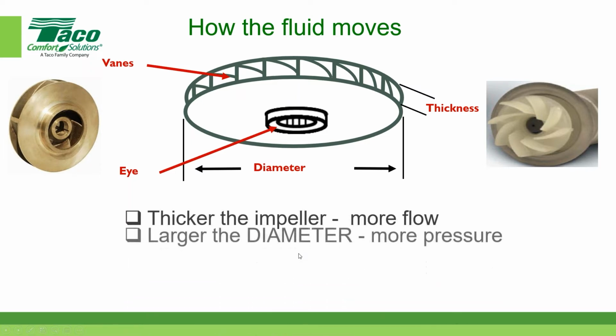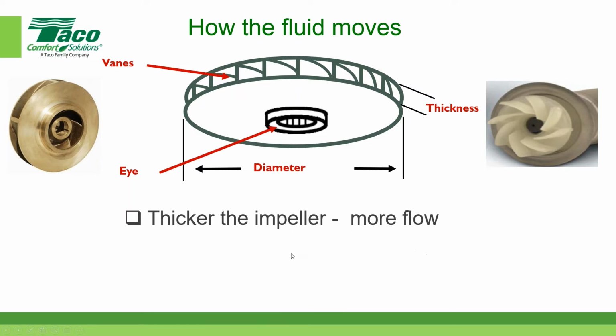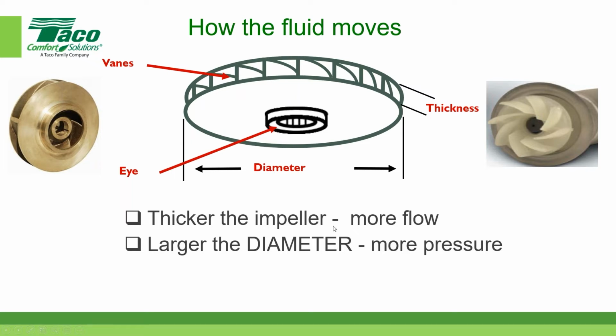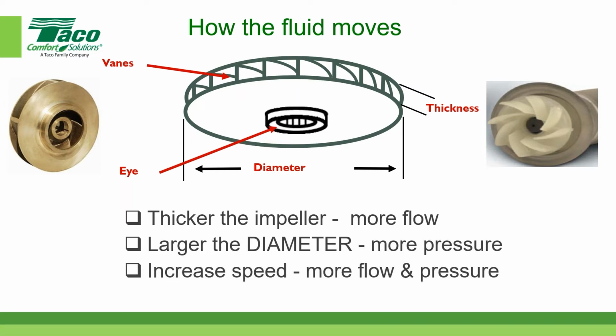Okay. So another thing to remember: the larger the diameter... well, let me reference something real quick. The thicker the impeller, the more the flow. Remember the bucket analogy with the little girl spinning it? This would be akin to how big that hole is. The diameter would be how long the rope was at a given RPM. That little rope that she had on the bucket, if it got longer and she stayed at the same RPM, you would get higher pressure at that orifice at the bottom of that bucket. Okay, and nowadays when we're talking about the variable speed capability of these high efficiency circulators, we increase the speed or decrease the speed, and we get either more or less flow and pressure at the same time. So just understand that's how those circulators are working.